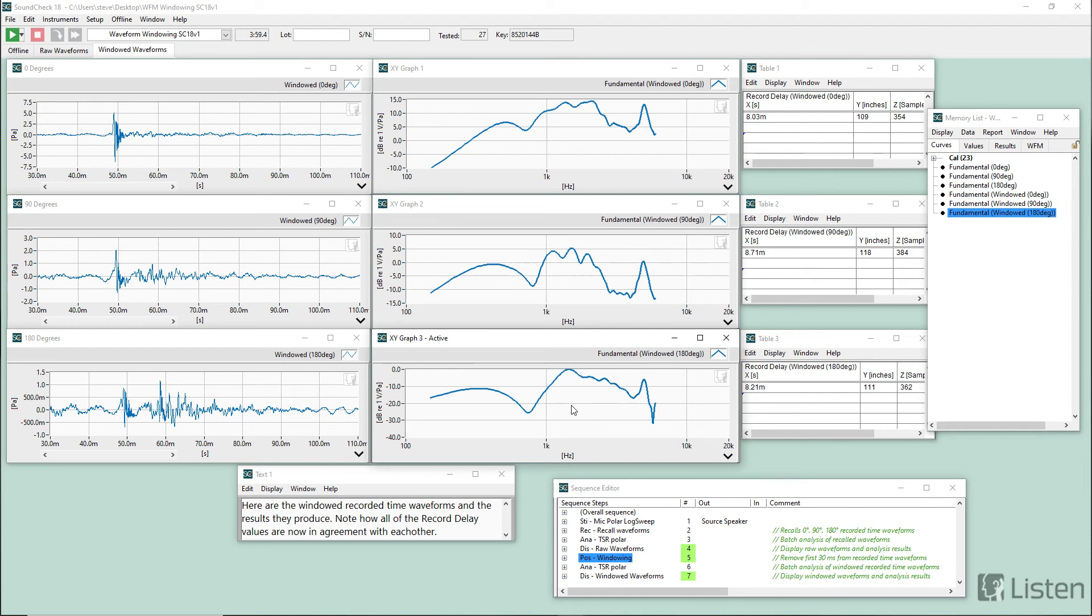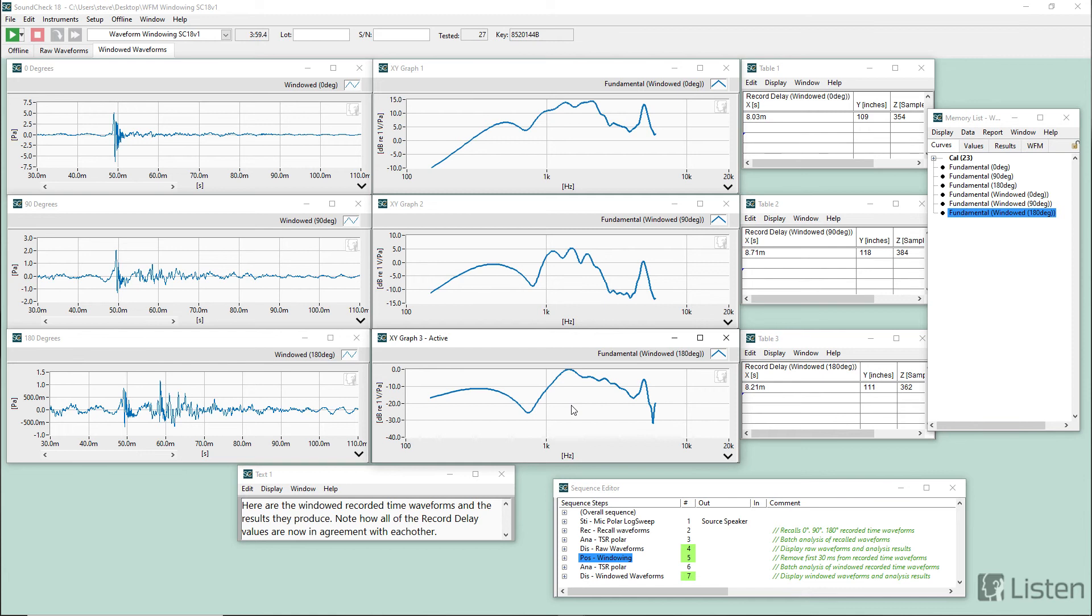So windowing can be a very useful function. There's another good example of it in your SoundCheck installation in the sequences folder in the subfolder for microphone example sequences. And that one is called open loop microphone. And that's actually a little bit more automated than what we're doing here because it actually takes a closer look at the waveform. And through a series of post-processing steps, it identifies the beginning of the recording of the stimulus and the end of the recording and windows it automatically. So it makes life a little bit easier.